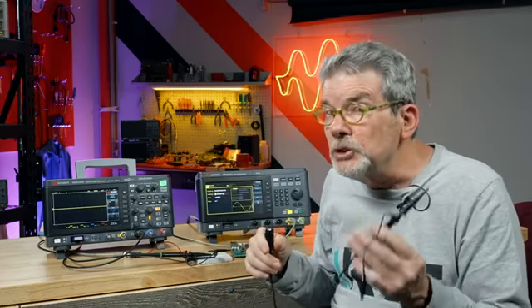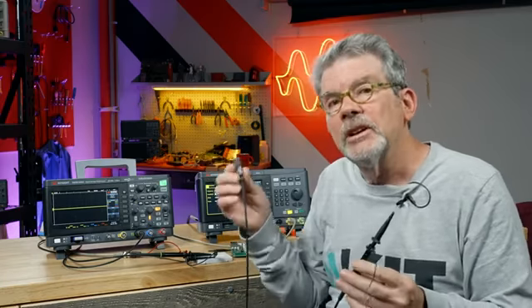So why would we want to divide the signal down by a factor of 10? There are 3 reasons. Number 1, you could measure larger voltages with a 10-to-1 probe. Number 2, and this is probably most important, a 10-to-1 probe has much higher bandwidth than a 1-to-1 probe. And number 3, you have higher input impedance. And what that means is less loading. Now, we can't go into a discussion of that now, but I'll reference an application note I wrote at the end of this video that you can download and learn a little bit more about probe loading.